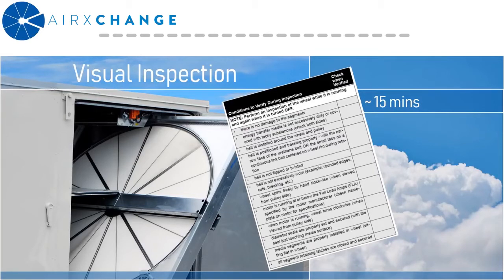You want to check the diameter seals and make sure that they're set properly. You want to make sure that the media segments are installed in the wheel and sitting flat, and make sure that all the segment retaining latches are closed and secure.